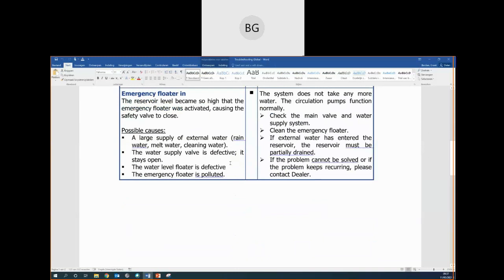Emergency float is in. The reservoir level has become too high. This means that there is a large supply of external water or rainwater or melted water from snow, perhaps cleaning water if you've had a separate supply in to clean the packages. Perhaps the water supply valve is defective and leaking, it stays open. The water level float itself is defective, or the emergency float is dirty or polluted. The system does not take any more water. So once the emergency float is in, the emergency valve will close and will prevent any more fresh water from being supplied.